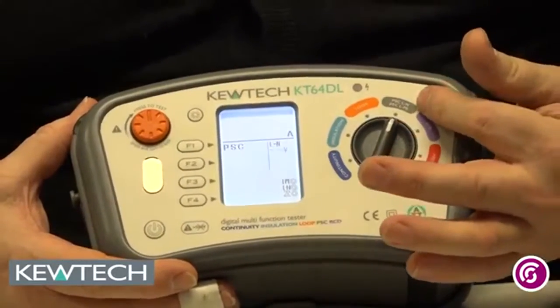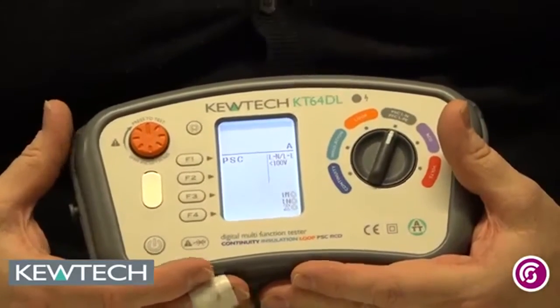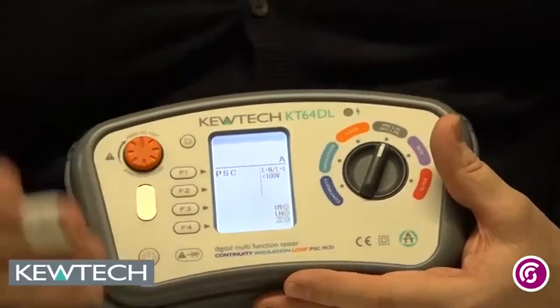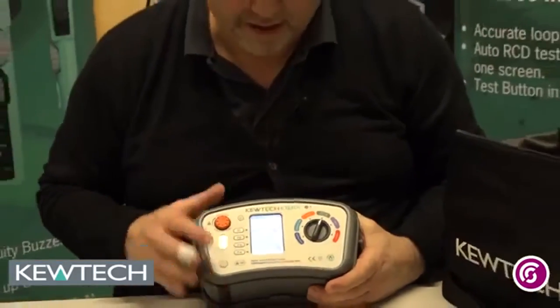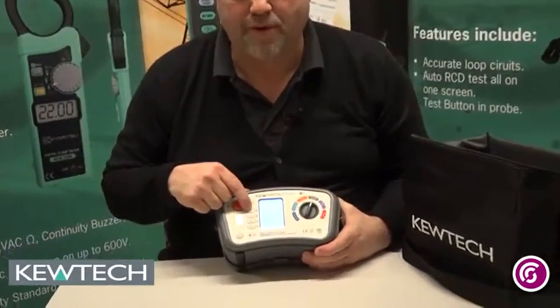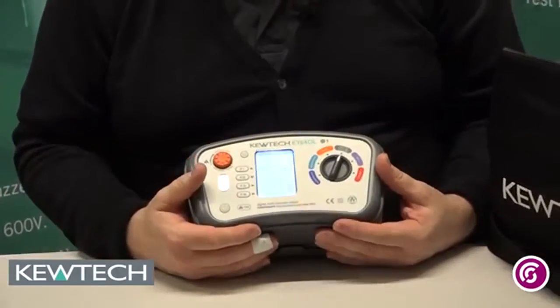Moving round to our fault current testing. Unlike other testers which display the actual current at the same time as doing a ZE or ZS, it's a separate test. Remember, the earth conductor is reconnected once you've done your ZE, so never write down those values because they'd be wrong. By pressing the F1 button, we can do it either to earth or to neutral. The highest measured value — remember — is your IPF value.